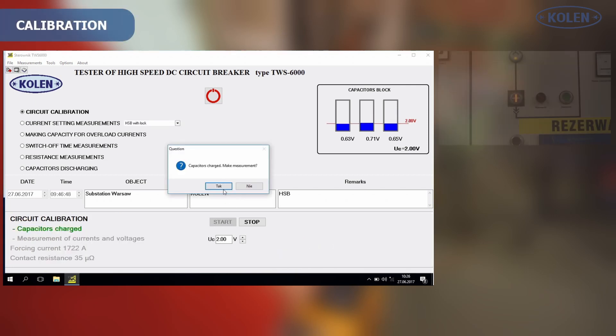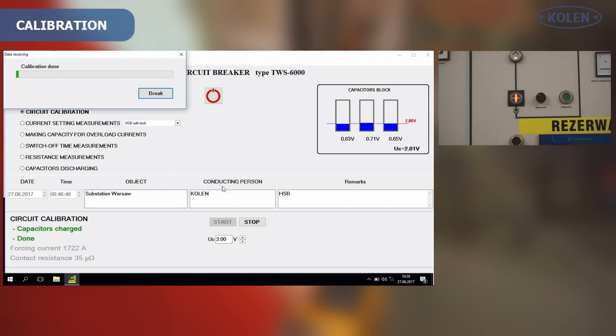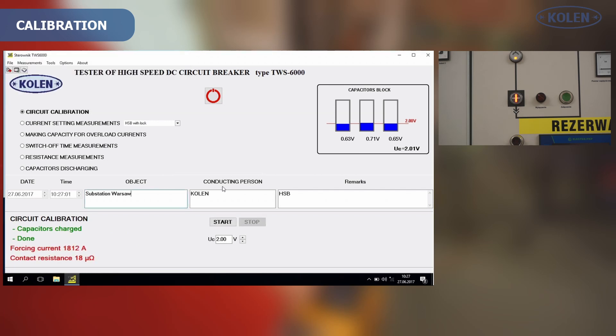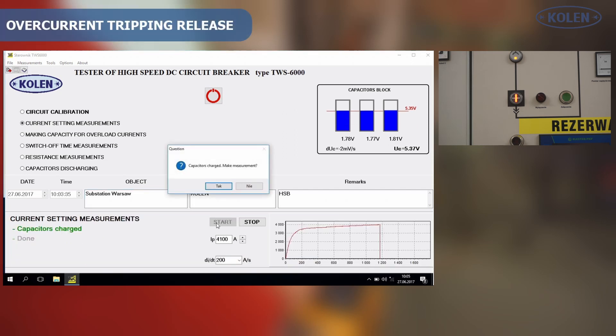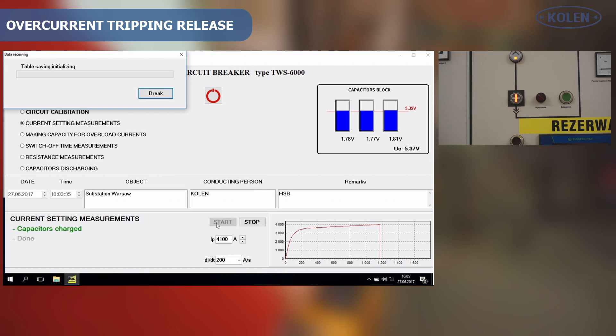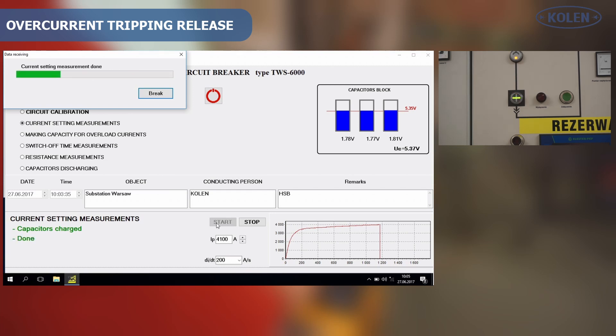Calibration of probing circuit is essential for accurate probing current value required in a given test. When overcurrent tripping adjustment is tested, the maximum value of probing current and its rate of rise can be varied, including 200 A per second required by the norm.